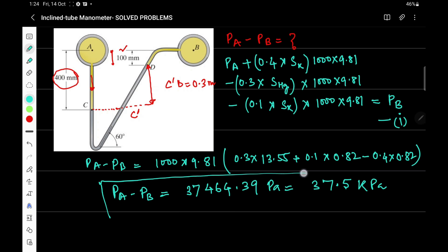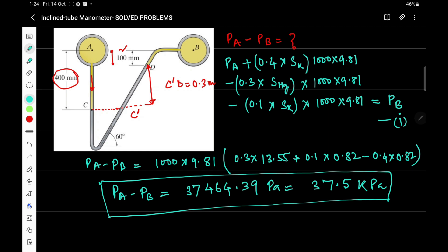In summary, for an inclined manometer, instead of measuring along the manometer tube, we must figure out the change in elevation between two different points. The angle and length of the manometer are given, and we calculate the elevation changes between the desired points. Inclined manometers are most applicable when the pressure change between two locations is very low. Note that the inclination from horizontal should not be less than 5 degrees, otherwise it becomes very hard to differentiate between the two meniscus levels.